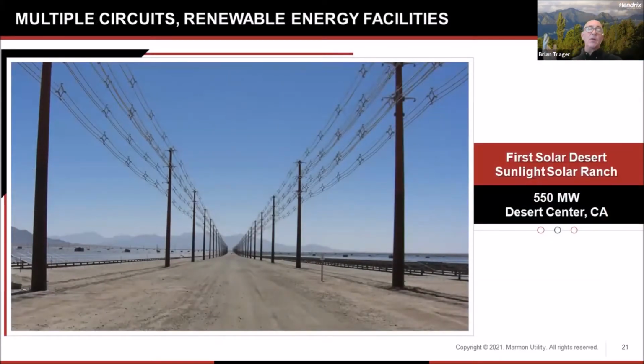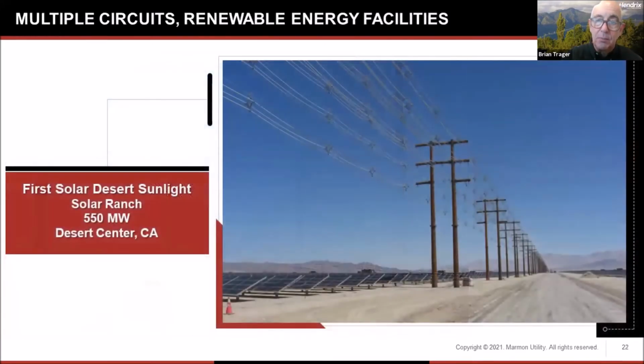And then as far as talking about multiple circuits or substation exits, we're using a lot in renewable facilities, whether they are wind or solar, and now with the batteries being added. So here is a site where we had 550 megawatts. We brought it all back to the substation with 11 circuits, each carrying 50 megawatts. And we got it on 2 pole lines. And here we've got 9 circuits on 1 pole line. So there's really an unlimited number of applications you can use spacer cable for in industrial facilities.